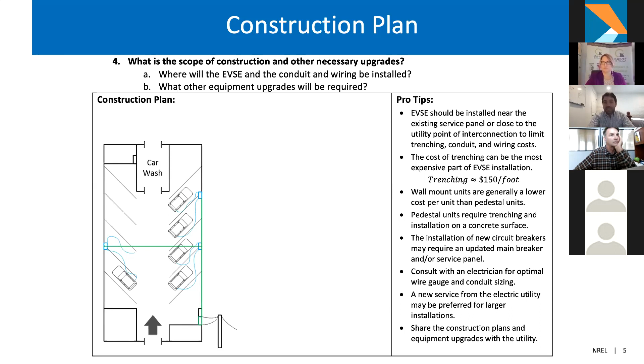You want to plan out what expansion or upgrades of service panels you require. As discussed previously, that means expanding the initial service panel and installing a new sub panel specifically for EVSE. You'll highlight the conduit, wiring, raceway, and service panel upgrades. Then you can have a great scope of the overall project to share with your utility and electrician, understanding the impacts before you even begin the procurement process for EVs or EVSE.